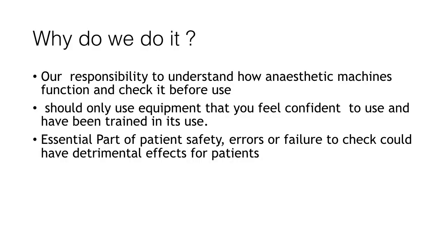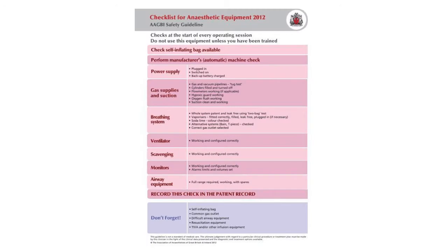So why do we check the anaesthetic machine? It is our responsibility to understand how the anaesthetic machine functions and check it before its use. We should only be using equipment that we feel confident to use and that we've been trained to use. It's an essential part of ensuring the patient is safe when we deliver an anaesthetic, as by checking the machine beforehand we can avoid errors that occur from faults within the machine which could have detrimental effects for patients. In 2012, AAGBI set out a safety guideline which outlines the checks that should be completed with regard to the anaesthetic machine and other anaesthetic equipment that we use. This slide shows you that checklist. We will now be discussing each element of the checklist in turn and how you check each component.